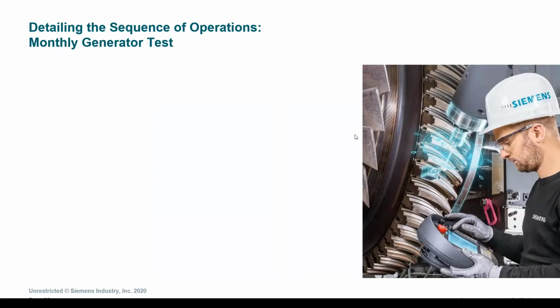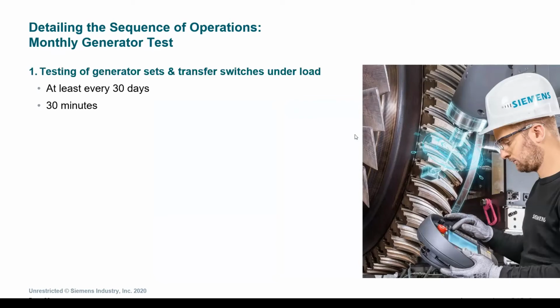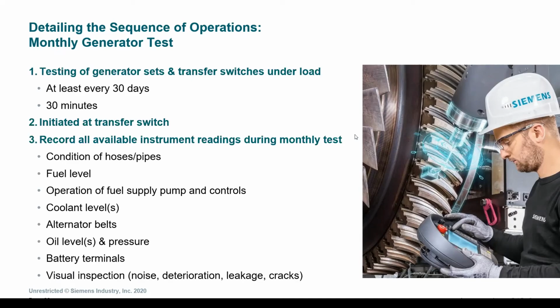From here, facilities, specifically healthcare facilities, also do monthly generator tests. The testing of the generator sets and transfer switches occurs under load at least once every 30 days. And this is done for 30 minutes. What happens is the test is initiated, typically at a different transfer switch each month. They don't have a different sequence of operation, but they do record all the instrument readings during that monthly test, from the condition of the hoses and the pipes, to the coolant levels, to actually visually inspecting all of the equipment.